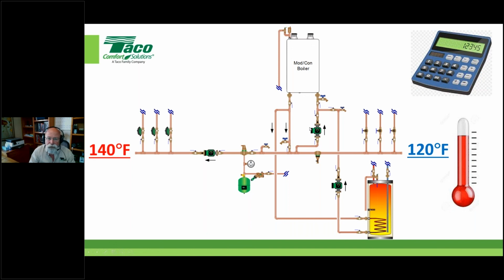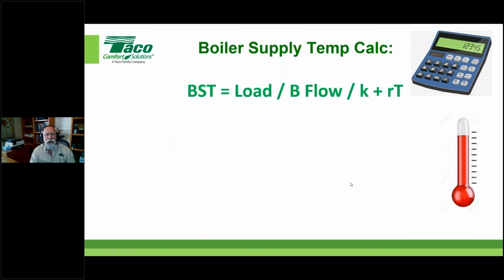We're going to simplify it pretty much. We know that we sized it at 10 gallons a minute based on a certain delta T, right? In this case, it was a 30-degree delta T. So here's how the calculation looks if you want to take notes. The boiler supply temperature would be equal to the load divided by the boiler's flow, divided by whatever constant you used based on the fluid type and temperature, right? And then you just add the return temperature, okay?